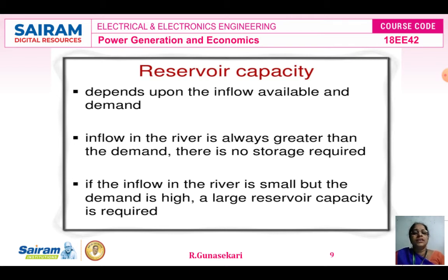The reservoir capacity depends upon the inflow available and the demand. That means the inflow, that is the turbine inlet, then the outflow of the turbine also. So for the reservoir capacity, if the inflow in the river is always greater than the demand, there is no storage required. If the inflow in the river is small, but the demand is high, our demand in terms of kilowatt or megawatt, so compared to the demand the river is small, then a large reservoir capacity is required for generating electric power by using a hydroelectric power plant.